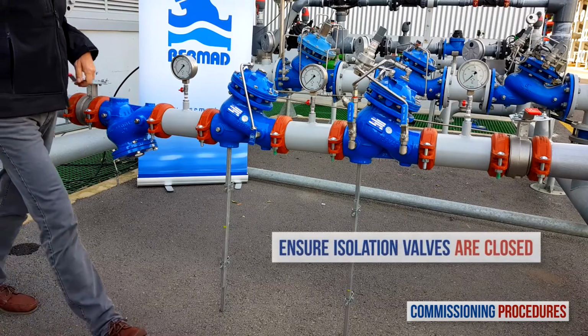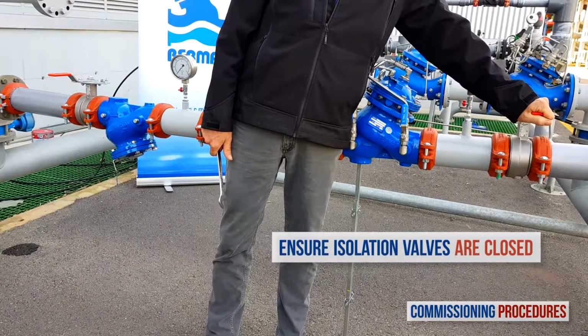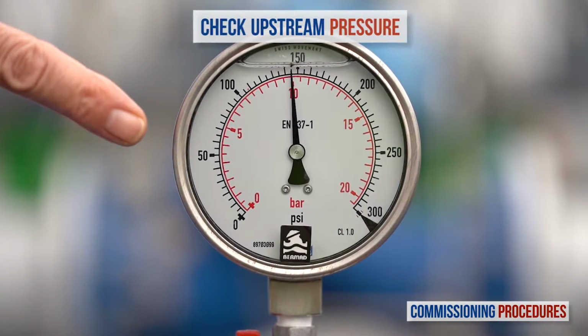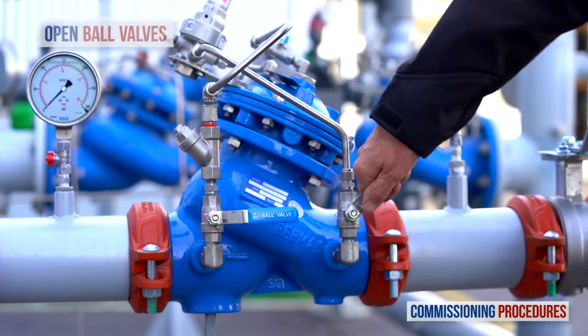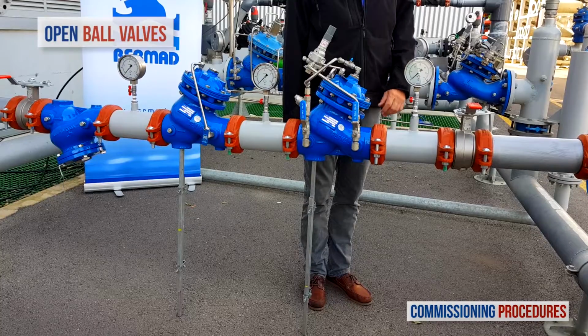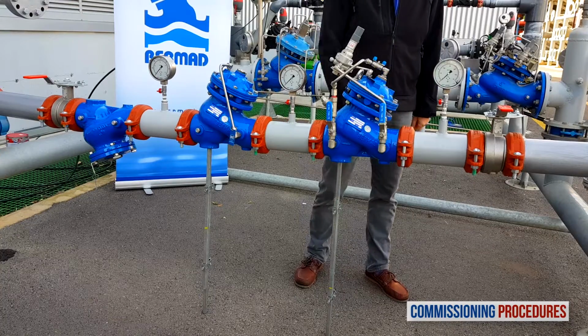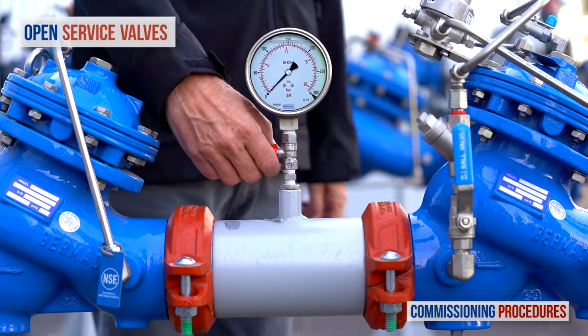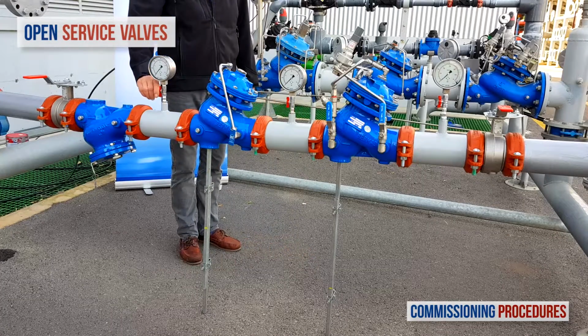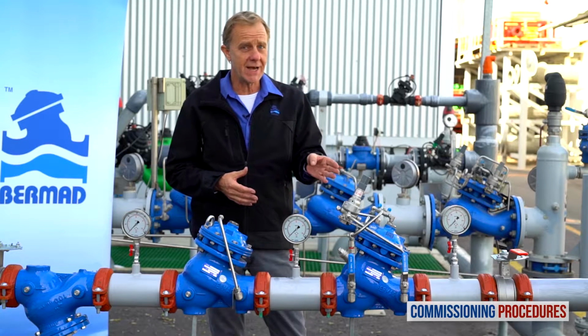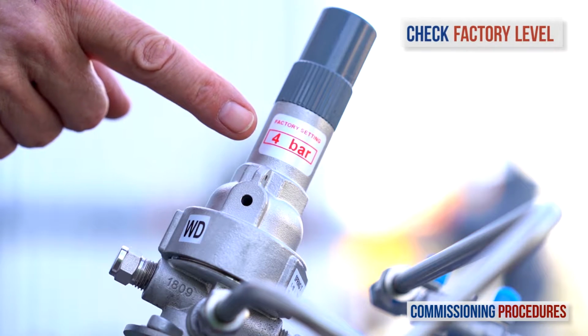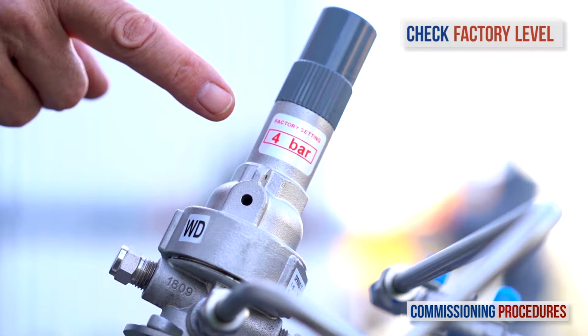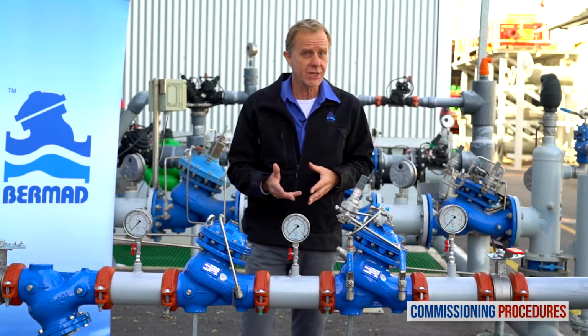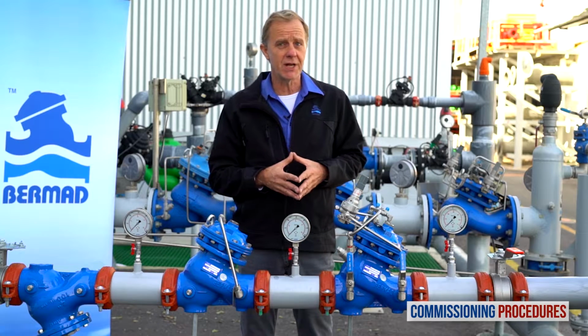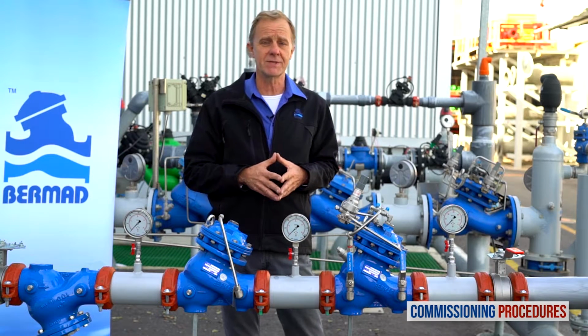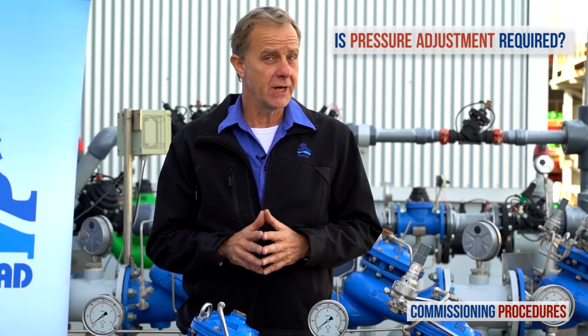Proceed by verifying that the upstream and downstream isolation valves are closed and that you have typical upstream pressure. Now open the ball valves on the secondary pressure reducing valve's control trim. Make sure that the service valves on all the pressure gauges are open. Note that the pilot of the secondary valve is calibrated at the factory. You can check the factory level by reading the label on the pilot cover. Before introducing flow into the station, you need to make sure that its preset pressure level is compatible with your downstream pressure requirements. If this is the case, you're fine, and you can leave it as it is.